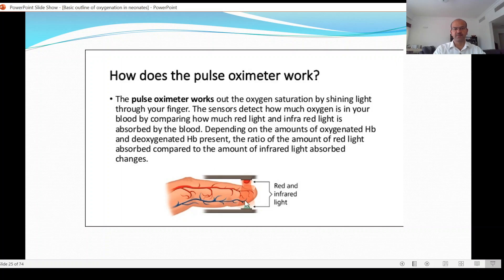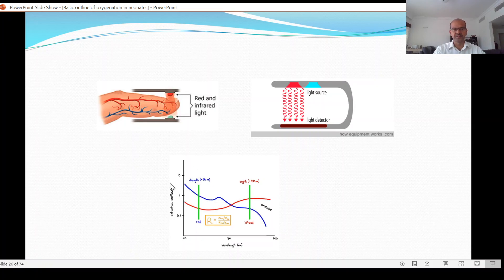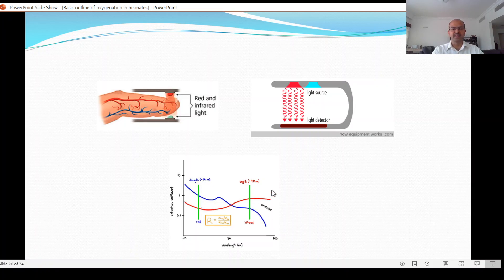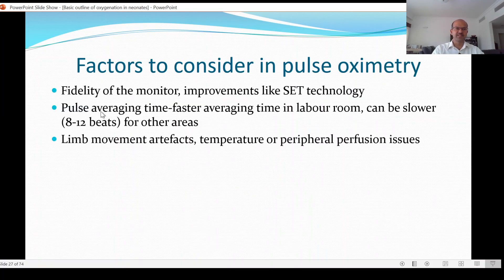You need pulsatile flow — the tips of the fingers are usually vascular unless the patient is hypotensive or cold. The pulsatile flow is extracted because capillaries and veins also contain hemoglobin. The sensors detect how much oxygen is in the blood by comparing how much red and infrared light is absorbed, depending on the amounts of oxygenated and deoxygenated hemoglobin. Different companies have slightly variable measurements for the same reading because their algorithms are slightly different.